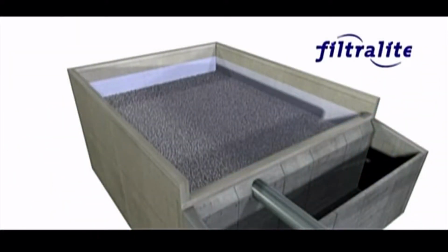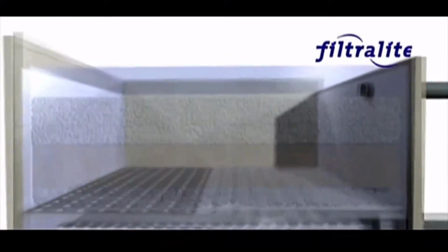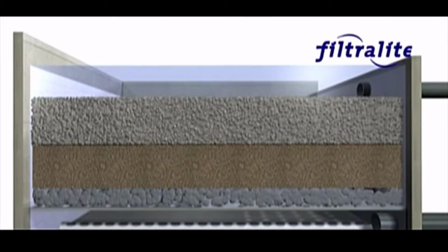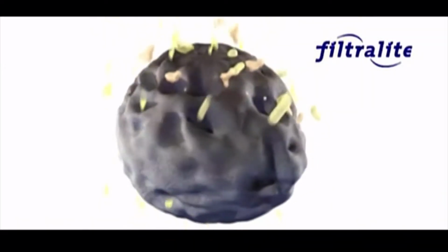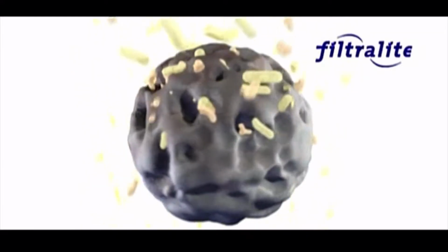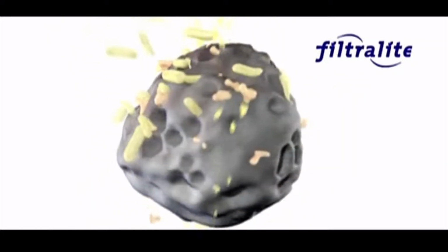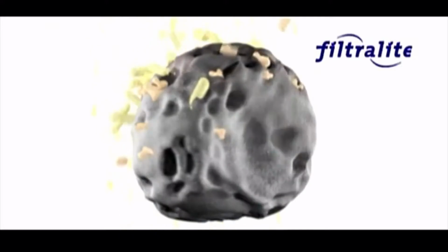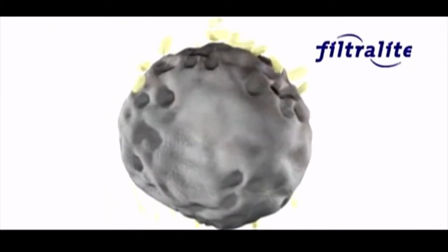As mentioned earlier in this film, Filtralite is used as a top layer over finer Filtralite. Compared to other filter media used for this purpose, Filtralite is very porous. This results in a very low head loss across this part of the filter. The material's porosity also gives a high storage capacity for suspended solids. These properties lead to considerably longer filter runs than for comparable filter media.